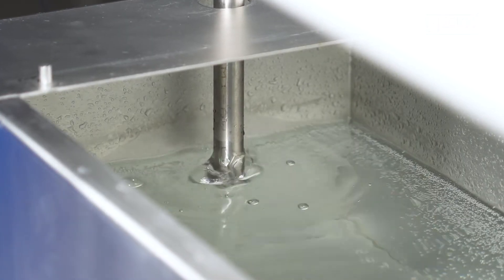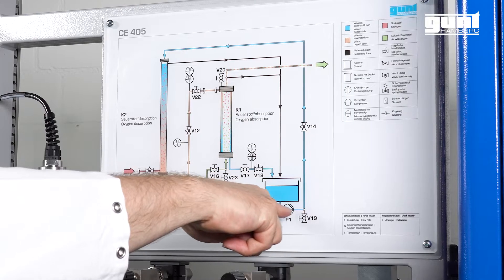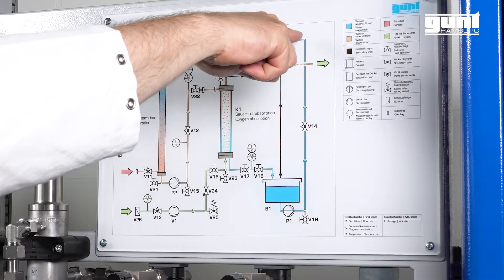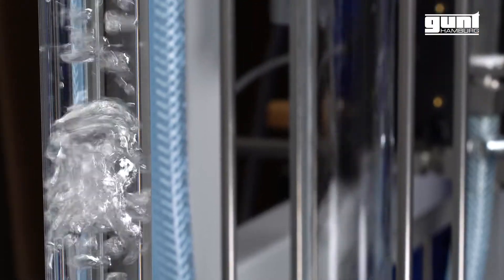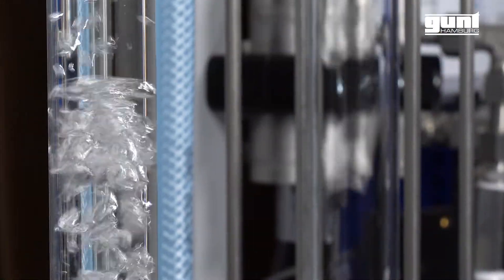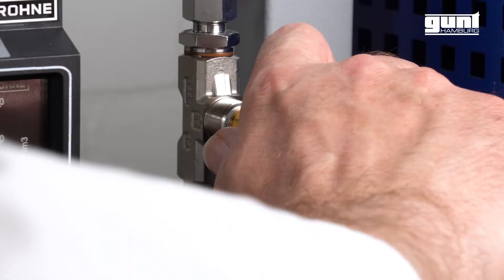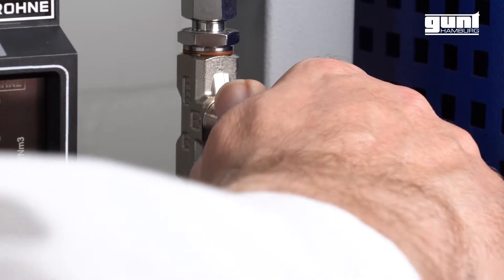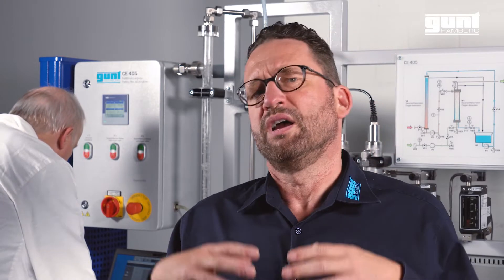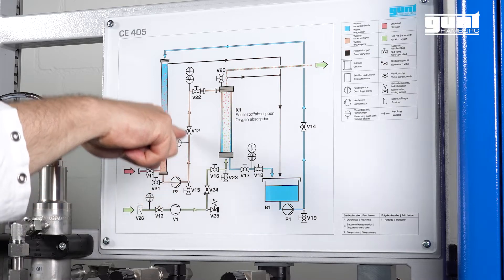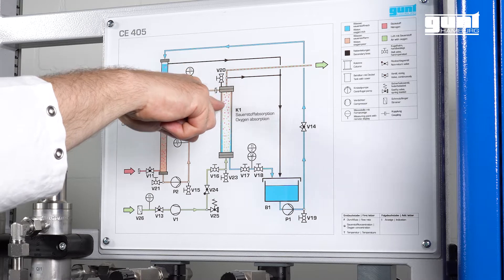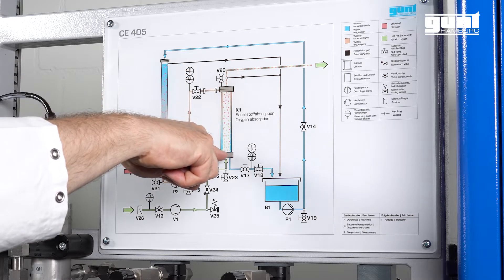The high oxygen content water is collected and transferred to the stripping column. The stripping — that is the desorption of oxygen — is done with nitrogen. In a continuous process cycle, low oxygen content water is taken out of the bottom of the stripping column and pumped back into the falling film column.